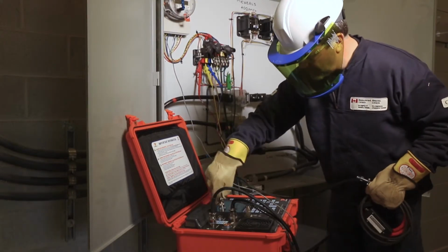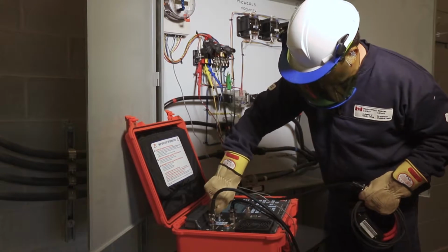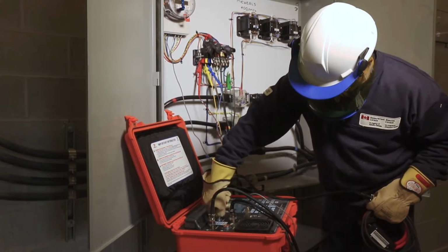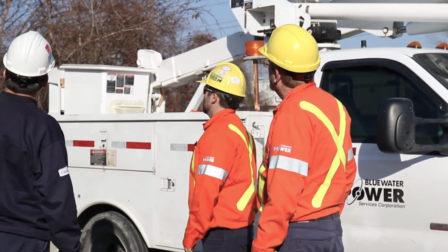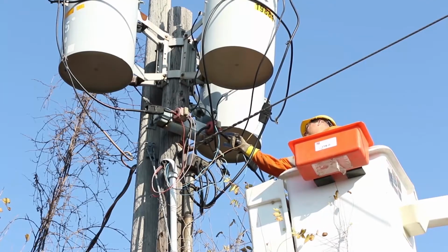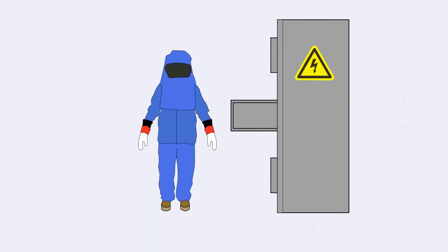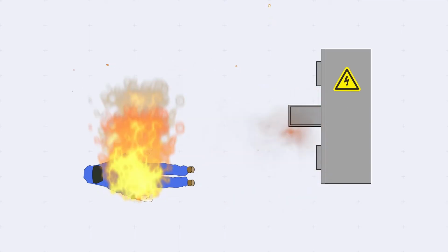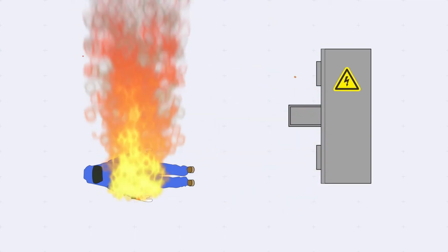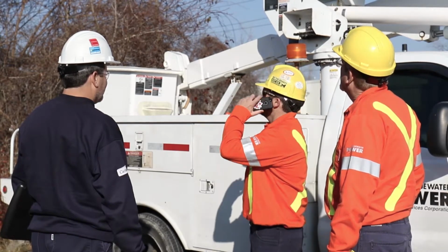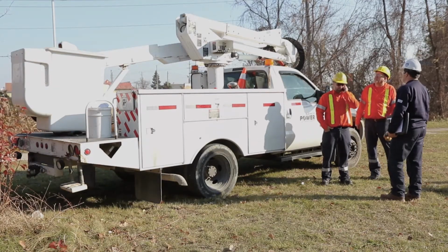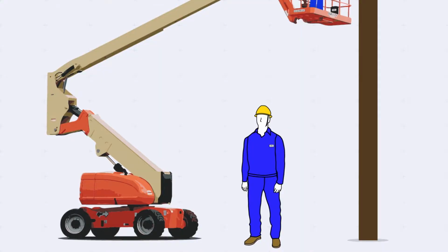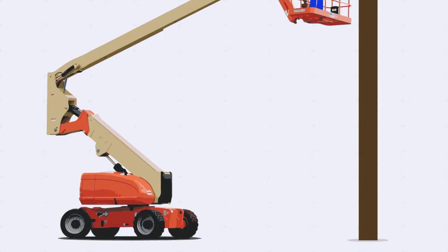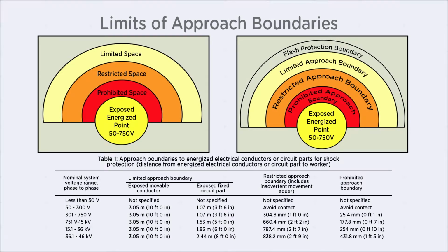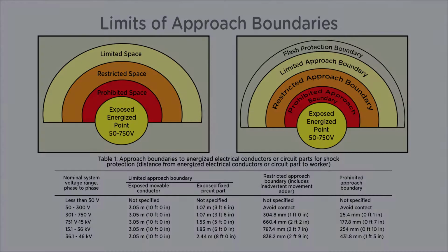Remember, Measurement Canada inspectors are only authorized and trained to test or inspect metering installations and are not authorized to perform work or repairs on metering installations if they are energized. Measurement Canada inspectors are typically not equipped with the appropriate arc flash rated clothing to be protected from the incident energy created from an arc flash. If work has to take place on the metering installation or line maintainers are performing work at the site, the inspector has to be aware of their limits of approach and move well back of the flash protective boundary. The following table outlines the limits of approach boundaries to energized electrical conductors or circuit parts for shock protection.